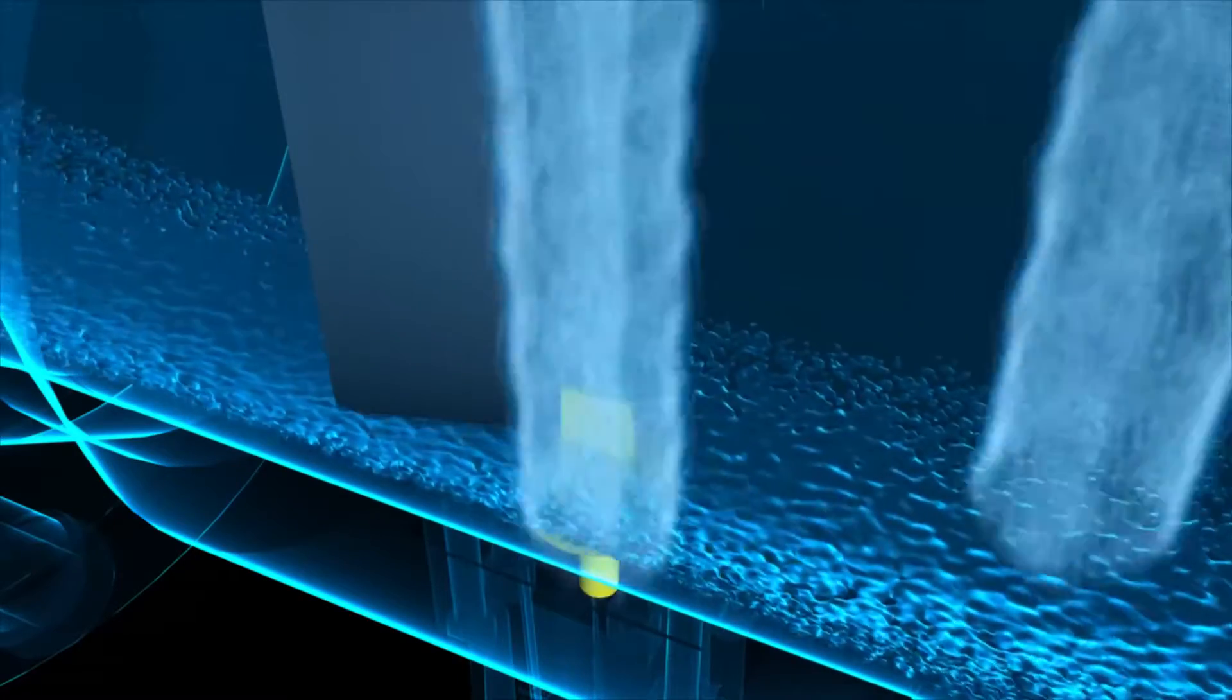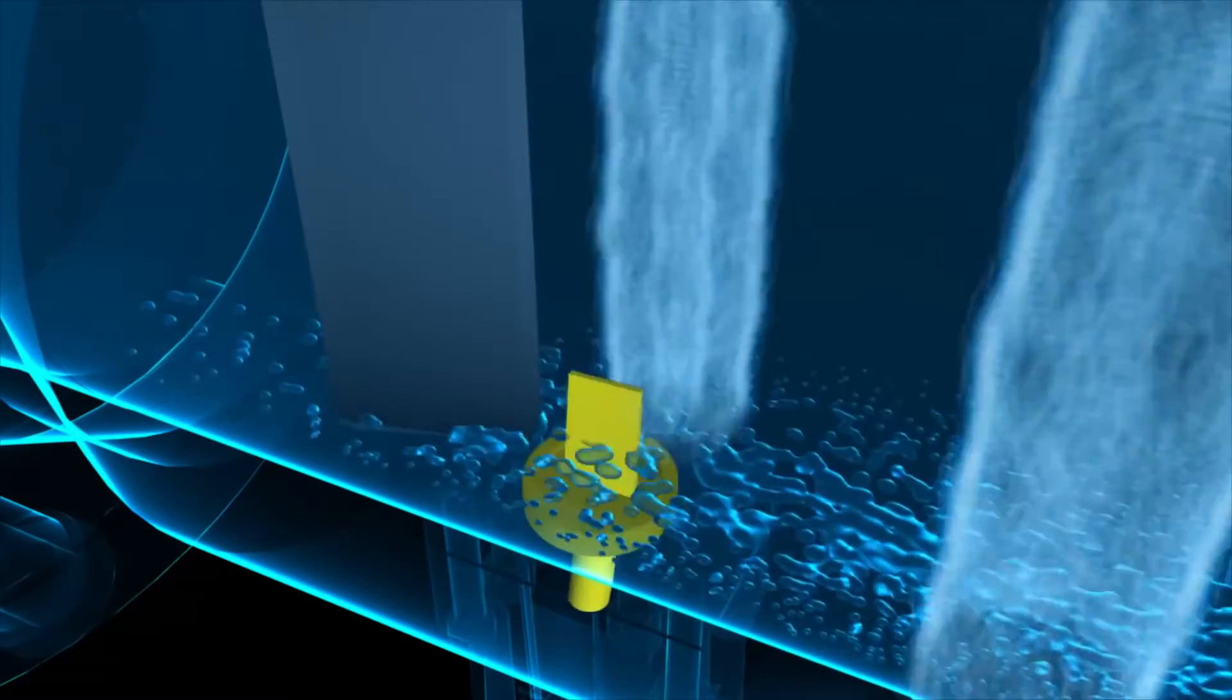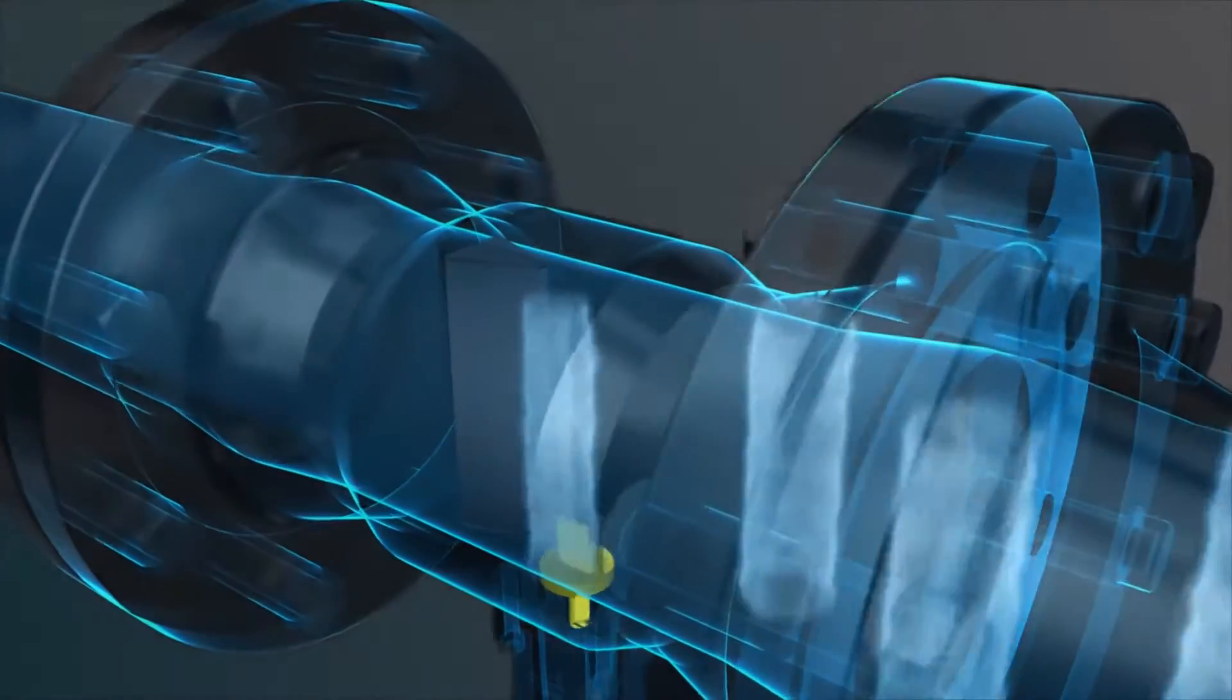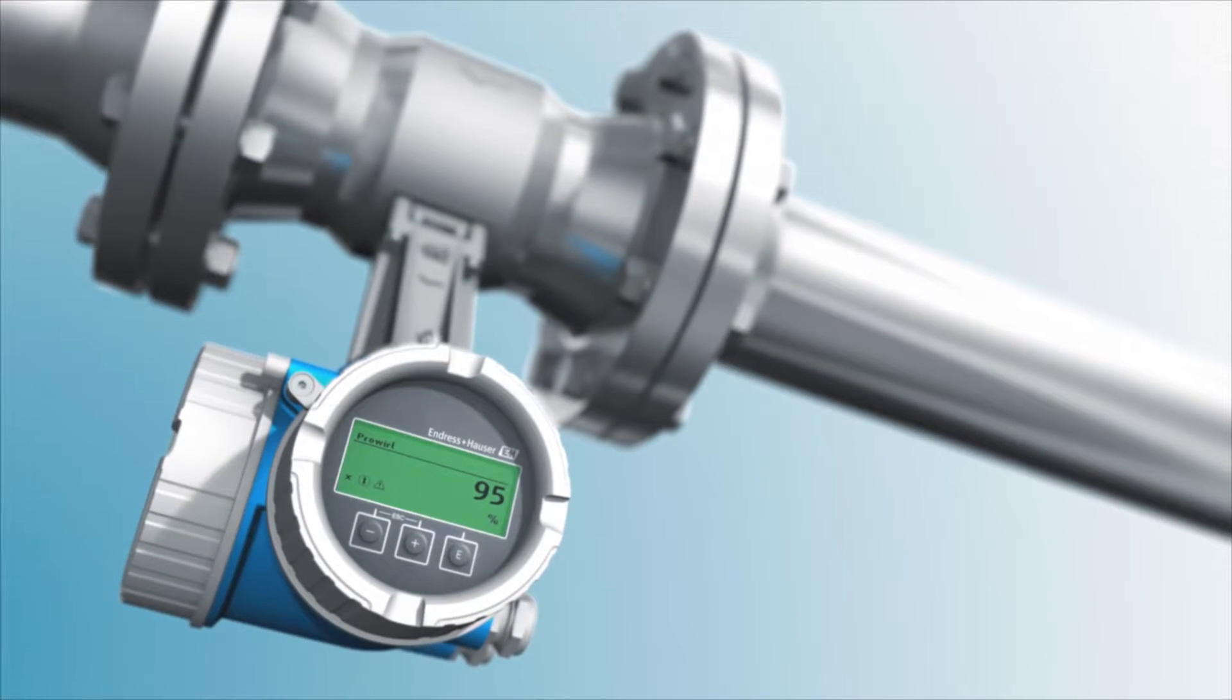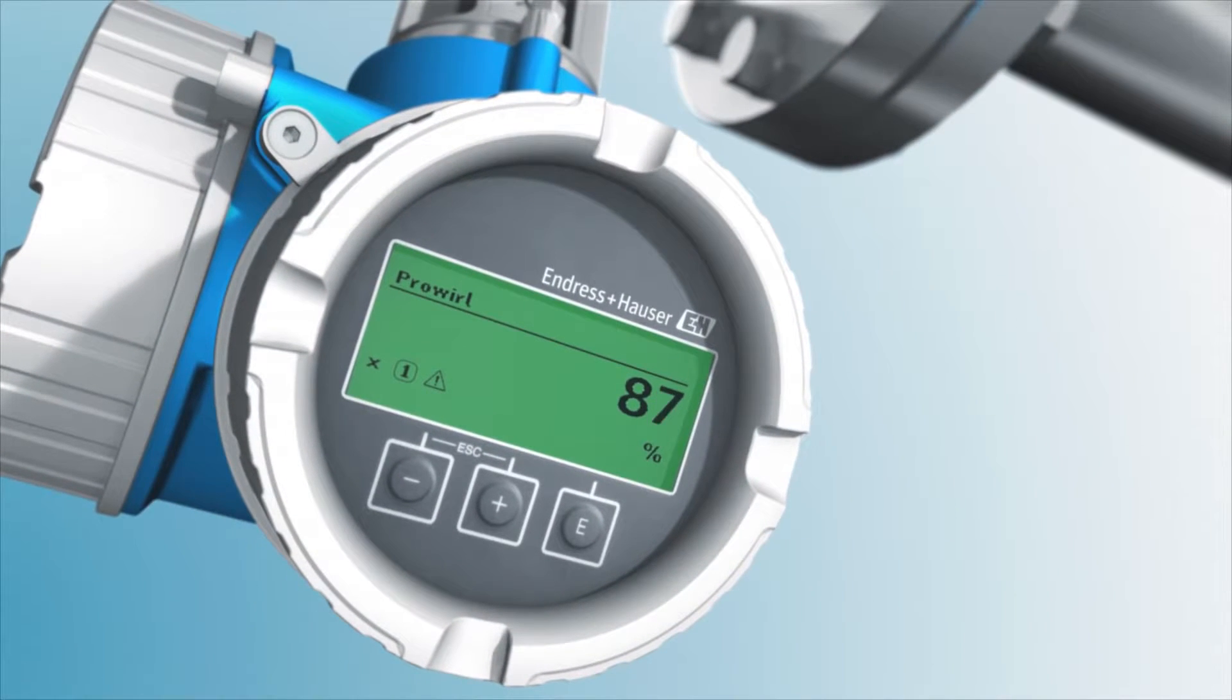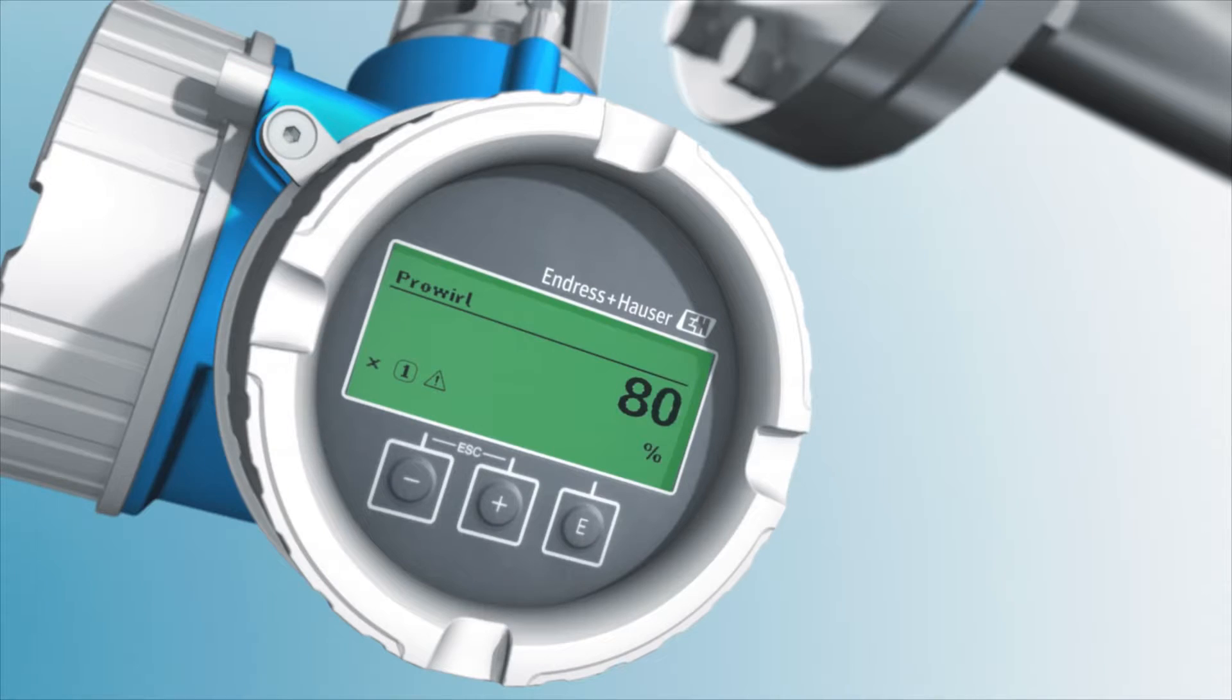Consequently, Prowirl 200 can directly measure not only the steam's dryness fraction, but also the corrected actual amount of steam. These measured values, dryness fraction and actual amount of steam, are permanently shown on the device display. If the dryness fraction of the steam falls below a specific freely selectable value, though with a minimum limit of 80%, then Prowirl 200 generates an automatic warning signal. This means you are always aware of the condition of the steam in your pipe, and also able to decide whether specific countermeasures are necessary.